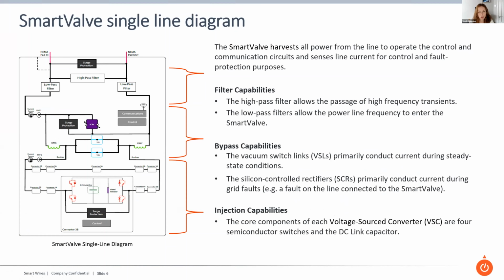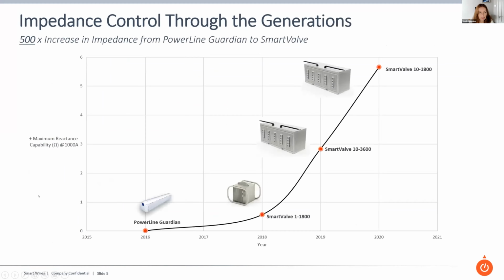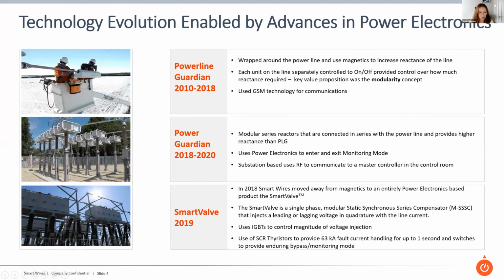Each of those converters has an option in the technology to be individually bypassed. So if you have a fault on one converter, the other 9 converters can remain injecting without employing this major bypass system here. So at an individual SSC module level, you can have bypasses on the individual converters. And then when you look at the installation here, where you've got, in this case, 2 per phase, but we have installations with up to 7, 8, 9 per phase, if one of these is bypassed, the others are all still actively in series. If you just go for a modular level bypass, the remaining devices remain in service, and then we have a control system which will balance that across the 3 phases, because this is a single phase device.